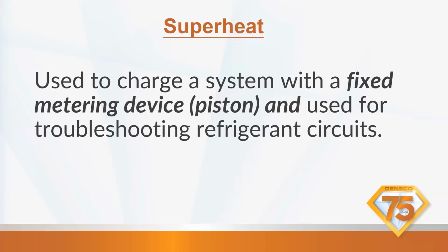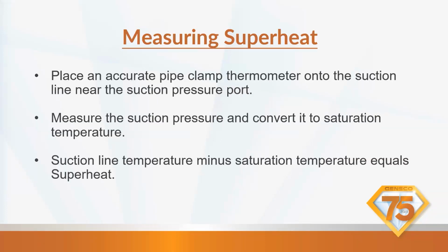It's used to charge a system with a fixed metering device and used for troubleshooting refrigerant circuits. We always want to make sure that we have some superheat going back, not too much, because then it uses the refrigerant cooling to cool the compressor. To measure superheat, you place an accurate pipe clamp thermometer onto the suction line near the suction pressure port. In AC, you can take this on the middle leg of the reversing valve on heating. You measure the suction pressure and convert it to saturation temperature, which I have a slide on next. Your suction line temperature minus saturation temperature equals superheat.